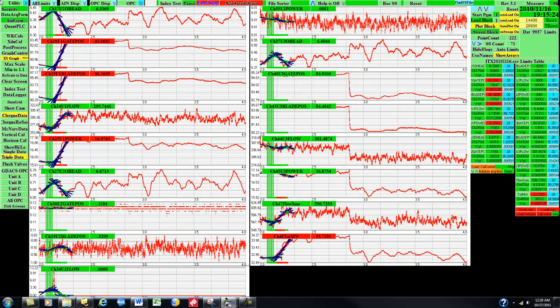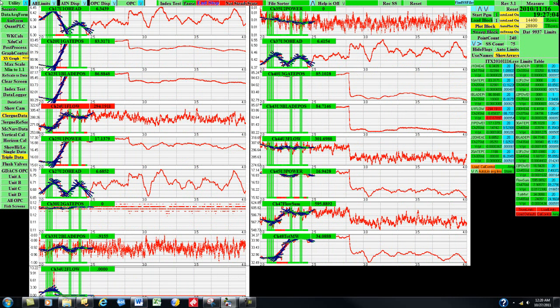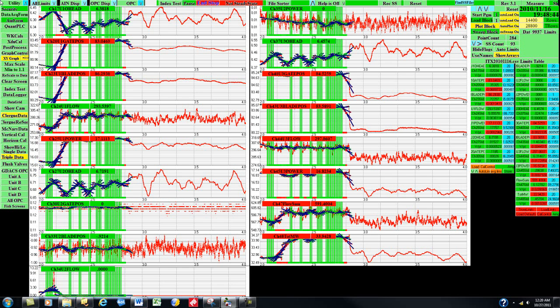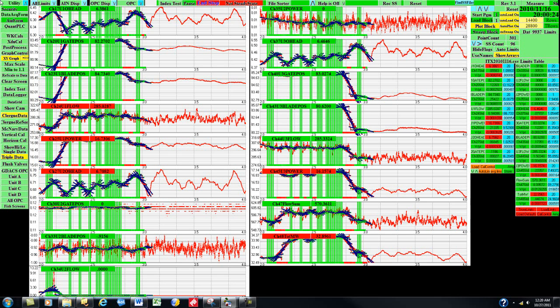At each step, the steady-state algorithm performs a linear least square fit to draw a best fit line through the center of mass of the data in each 1,000 sample parse, the results of which are an average value and slope of the line. A second pass calculation of the square root of the sum of the squares, or RSS, derives a standard deviation value to quantify the noise between the measured data points and the best fit line.